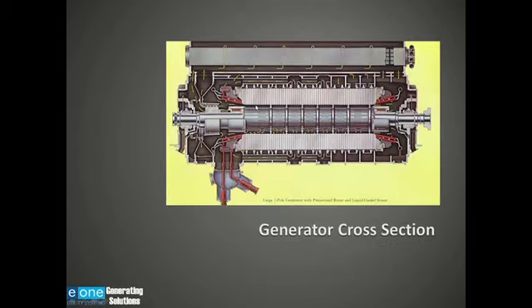Here's another section view of the generator, and the reason I put this up here is to show the hydrogen circulation, because we're going to be discussing hydrogen a lot and how it circulates through the generator. You can see the yellow arrows, and these yellow arrows represent the path of the hydrogen and the cooling. And you can see that the hydrogen is cooling the stator. It flows through the stator windings. It flows through the rotor, under the retaining rings. This device up here is a hydrogen cooler. That's a heat exchanger that removes the heat from the hydrogen. And as I mentioned, some generators have fans, some have blowers. This particular one has a blower, and that's what circulates the hydrogen in this generator as long as the rotor is rotating. And here is a hydrogen seal on this particular generator.